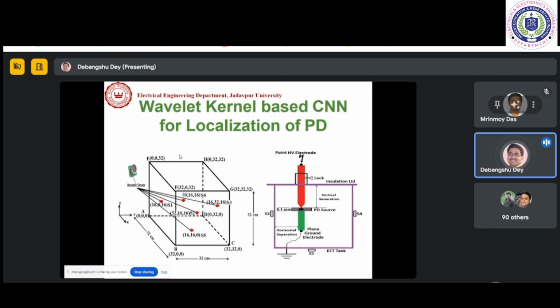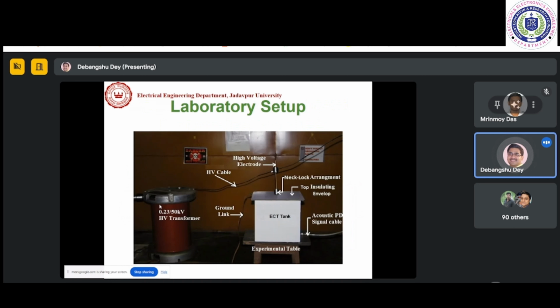The red dots are the sensors - here I am showing you the acoustic sensors. They can be fitted on the walls of the transformer. Those red dots will capture some signal, and from those signals you have to find out the location of the partial discharge. As the location can be so many, my problem is now a little bit more complex. So this is the particular setup.